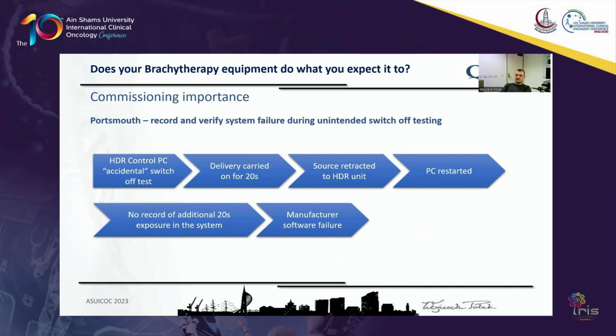They didn't envisage the PC going off during the delivery. So that was actually something that stopped us from releasing the equipment to clinical use, and the manufacturers actually had to act and change the software to make sure that before we go live, this won't happen.